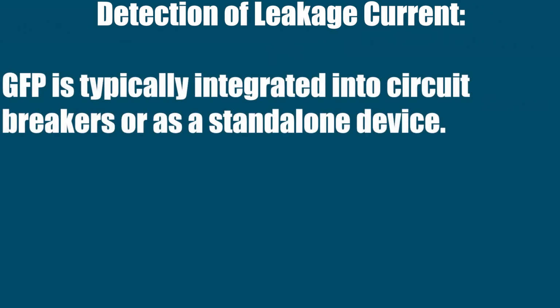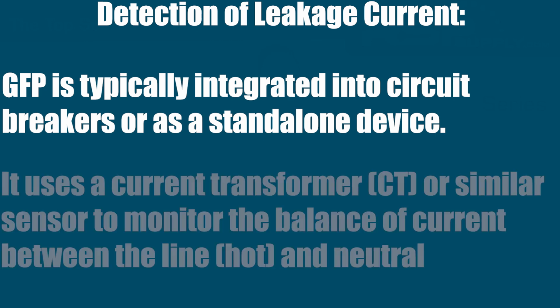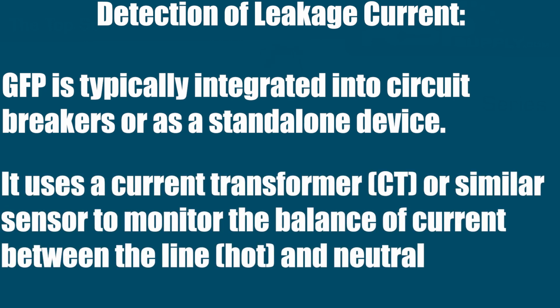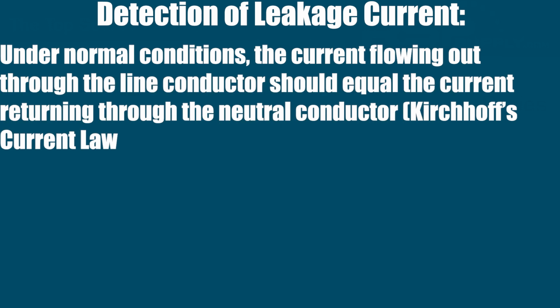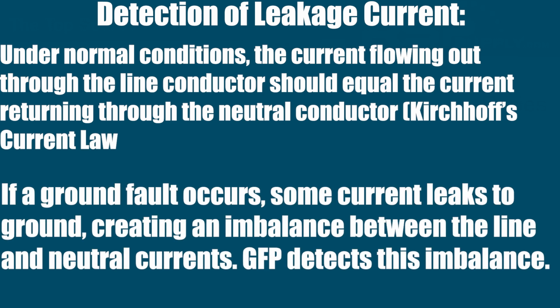First off, there's detection of the leakage current. Ground fault protection, or GFP, is typically integrated within circuit breakers or as a standalone device. It uses a current transformer, or a CT, or some other similar sensor to monitor the balance of current between the line, the hot line, and neutral conductors. Under normal conditions, the current flowing out through the line conductor should equal the current returning through the neutral conductor. That's part of Kirchhoff's current law. If a ground fault occurs, some current leaks to ground, and this creates an imbalance between the line and neutral currents. GFP detects this imbalance.